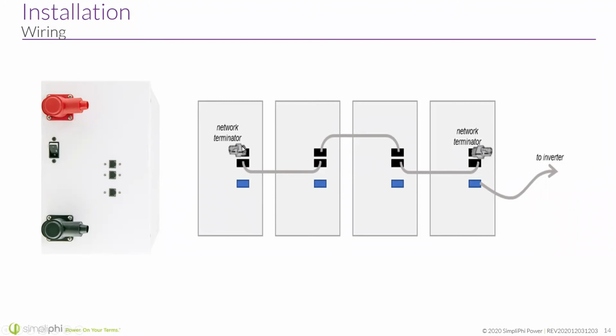So this bank of 4, we can see where the batteries have been terminated, and then they're connected to each other using those Cat5 cables, so in and out here, and then terminated again. These are dust caps, so we would have a dust cap here, a dust cap here, and a dust cap here. We only need one cable from one battery to the inverter.